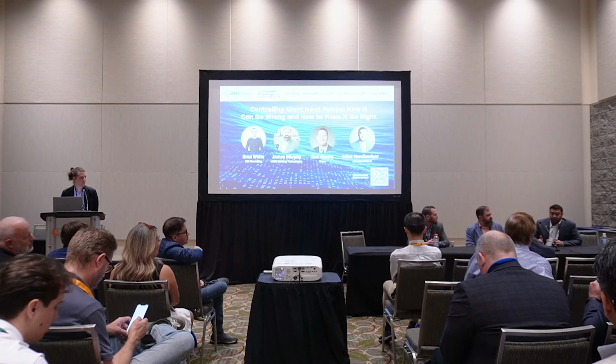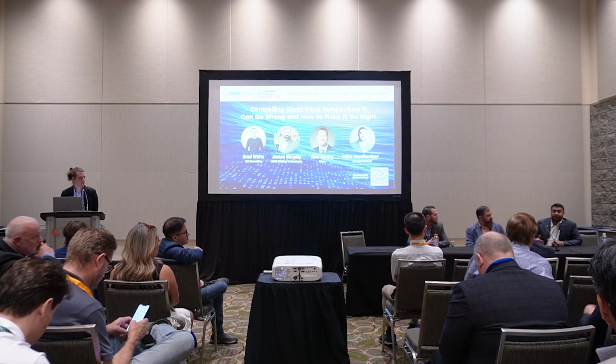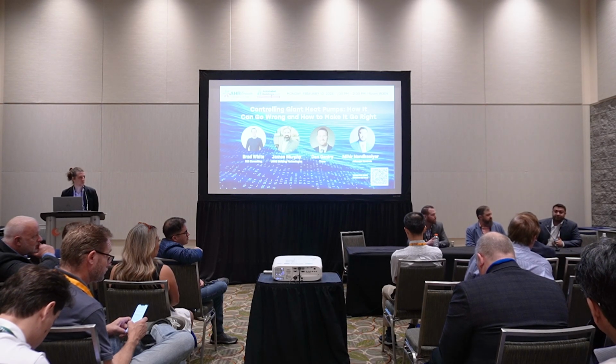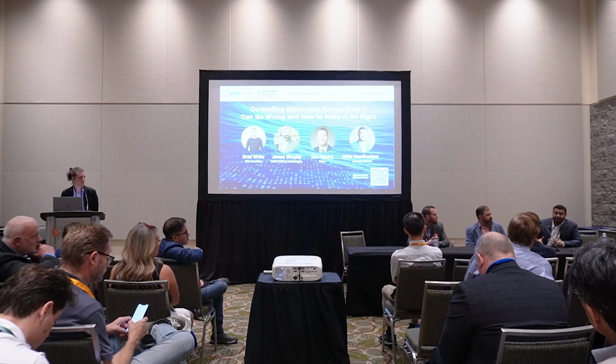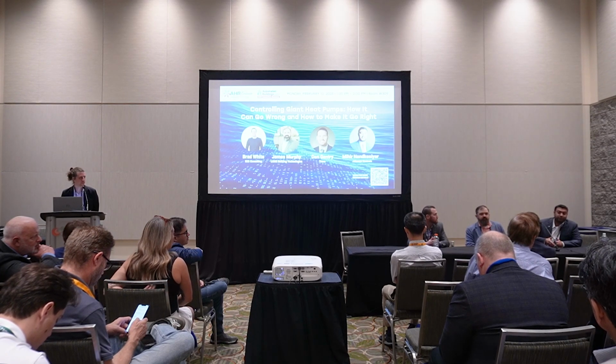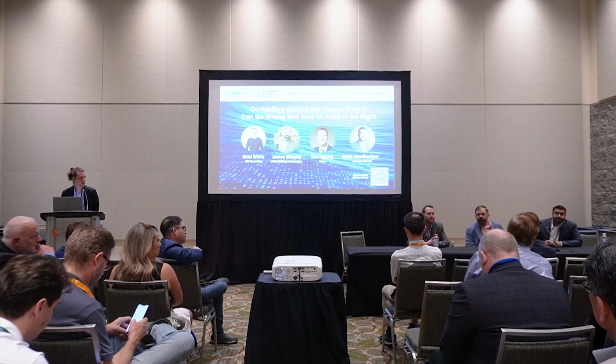I guess what I'm saying is, if the difference between the 1% and the 0.2% is 20 degrees of ambient, that's a huge derate on an air source heat pump. You might double the amount of equipment on your roof. That could be solved maybe a little bit differently, potentially a little inefficiently, but the number of hours between that 1% day and the 0.2% day are so small in the life cycle of that building.